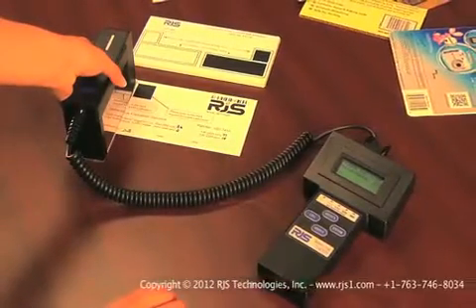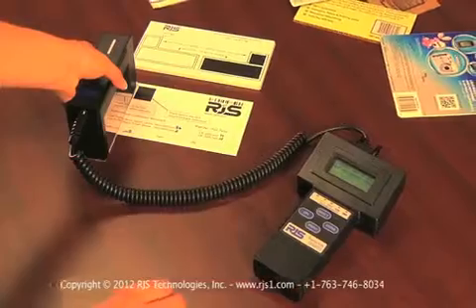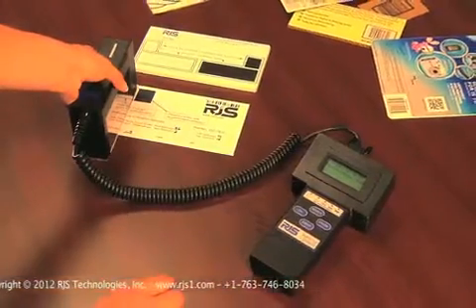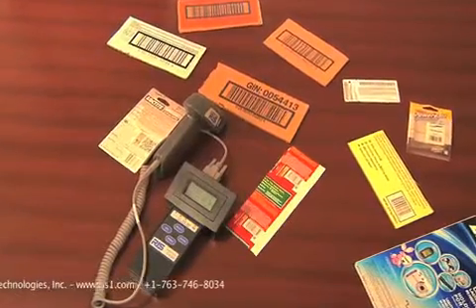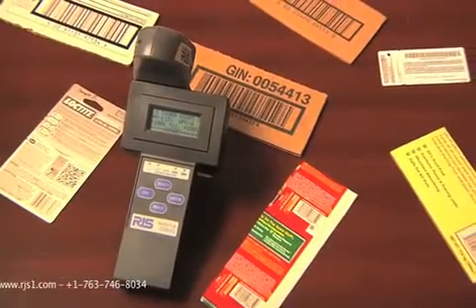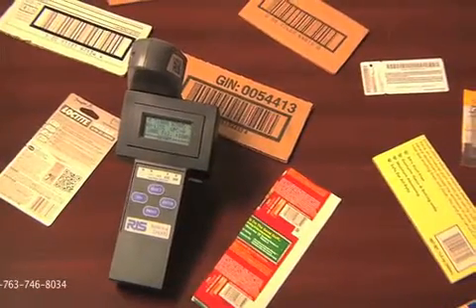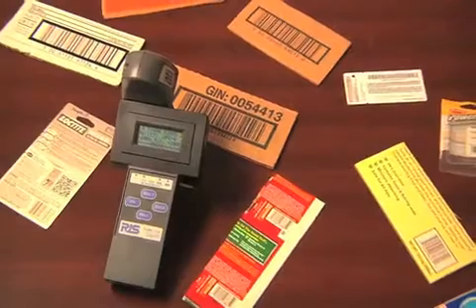It should be noted that this video only applies to the D4000 Auto Optic, as both the D4000 Laser and the D4000 SP do not measure reflected light, so they do not have a calibration procedure.